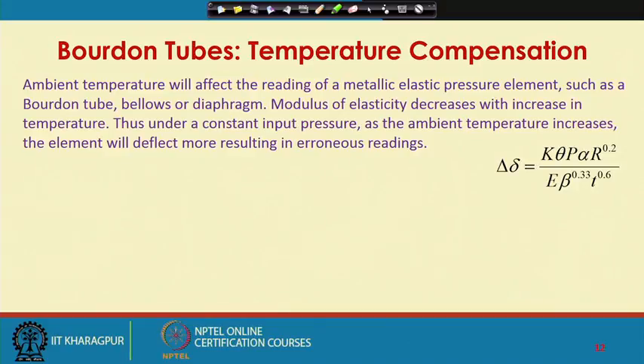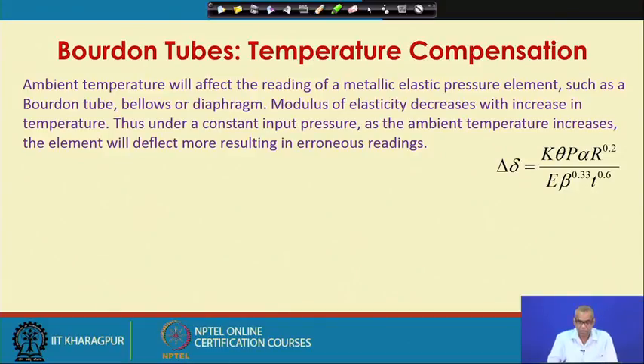So, one thing that can be done is you use Nispan C alloy to make your Bourdon tube, because if you take Nispan C alloy as material of construction, its modulus of elasticity does not change much with change in temperature. Another way of doing it is to make use of a bimetal for compensation of the effect of ambient temperature change. So, the ambient temperature will affect the reading of a metallic elastic pressure element such as Bourdon tube, bellows or diaphragm. So, this is common for Bourdon tube, bellows or diaphragm, because they are all elastic pressure elements and modulus of elasticity decreases with increase in temperature.